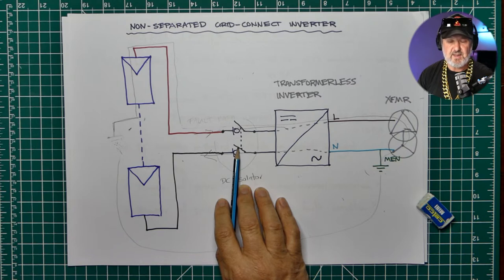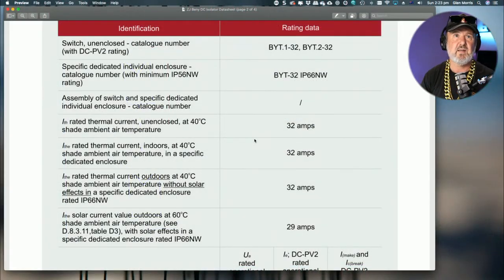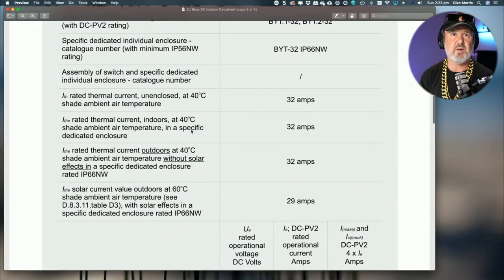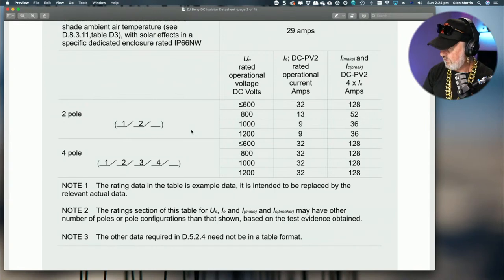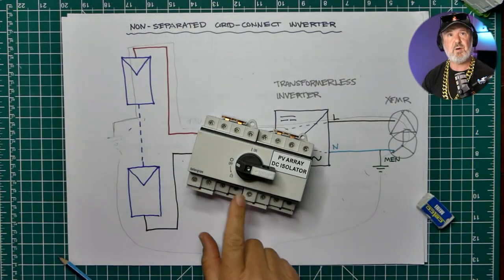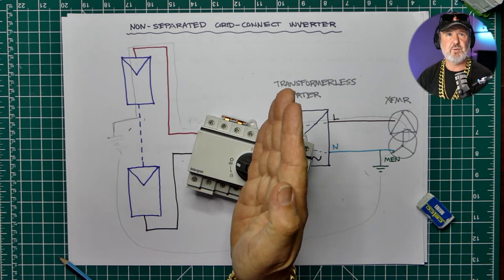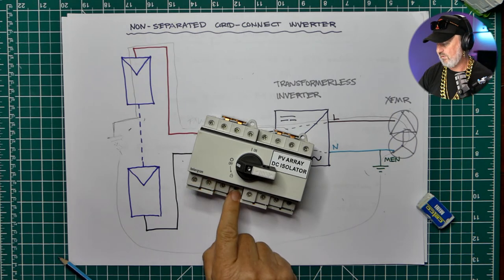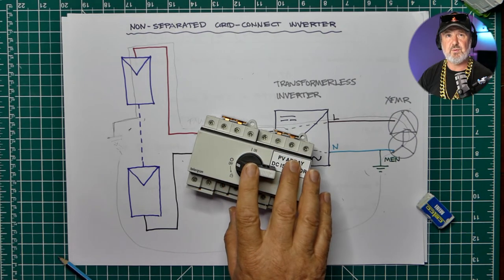But if we go and look at the data sheet for the ZJBeny, it actually has four switched poles. And if I go down to that, here we go. It's a four-pole device, not too dissimilar in terms of its configuration, but then something like half of one of these. Hang on, I'm just going to bring that one up. That's an 8-pole switch disconnector or isolator. If I had half of that, I'd have 4 switched poles. So 1, 2, 3, 4. And this one's an 8, so it's got another 1, 2, 3, 4. So on each side, I'm in this case switching 4 series poles.